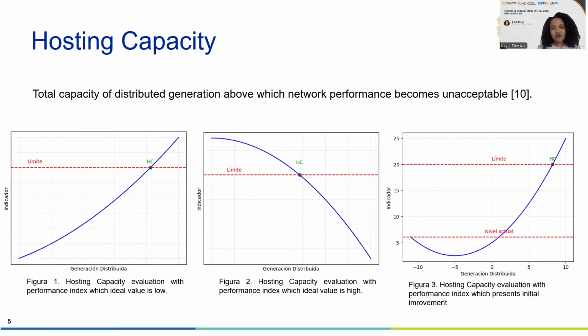In this sense, hosting capacity has been a term used since 2004, and that refers to the total capacity of distributed generation above which the network performance becomes unacceptable. It needs to be evaluated for each performance index of interest for the grid operator, and it will have different behavior according to the nature of the performance index evaluated.